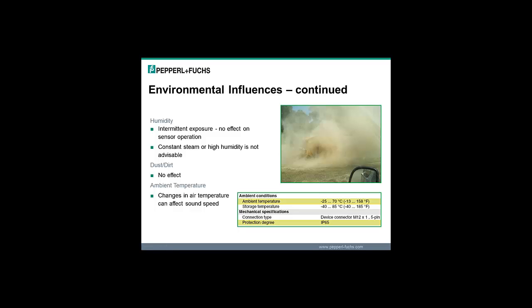A little more on environmental influences. Humidity. General outdoor humidity is not going to be a problem for any kind of ultrasonic sensor. The speed of sound may change a little bit, so your repeatability may change. But in general, these things are used outdoors all the time, so it's not really too big of an effect. But if you're in a constantly steamy or constantly high humidity environment, that could be an issue. If the sensor is exposed and over the course of a day, or 2 days, gets its chance to dry out, you're not going to have a problem. But if you have a steamy hot liquid and an ultrasonic that's constantly exposed to those vapors, that could be a problem over time.